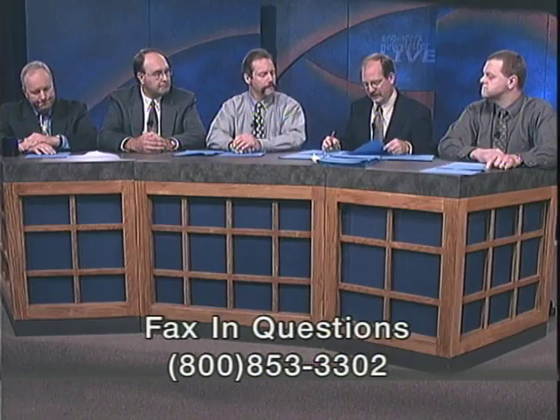In addition to the specific distances that are listed, there is an exception that you can use for packaged equipment like rooftops, where if you can demonstrate that, due to the direction and the velocity at which you're discharging the air, it is not re-entrained into the outdoor air, that would be acceptable. Okay. Thanks a lot, Gary.